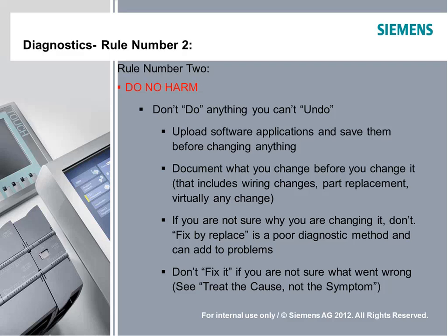I've been in situations where people have replaced parts that are programmable or have some kind of configuration switches on them, and now you've got another problem on top of the original problem, and trying to diagnose two issues is much more difficult than just the original one. So fix by replace is really a poor diagnostic method. And if you're not sure what went wrong, then don't start trying to fix things. We're going to talk a little bit later about treating the cause, not the symptom.